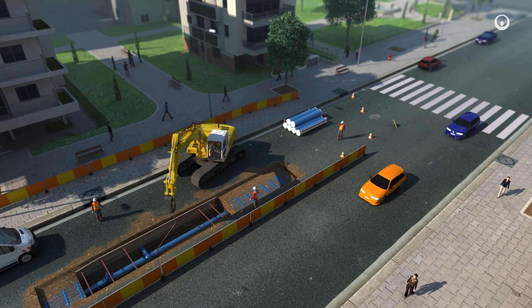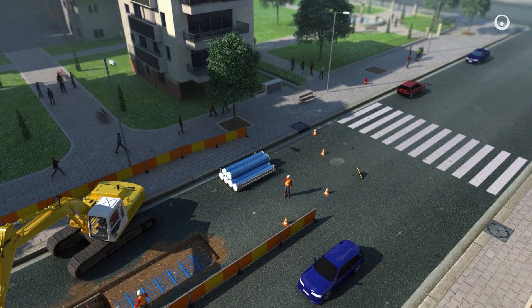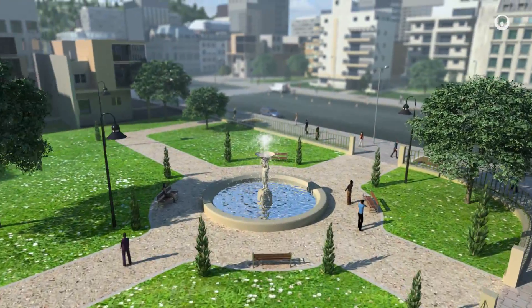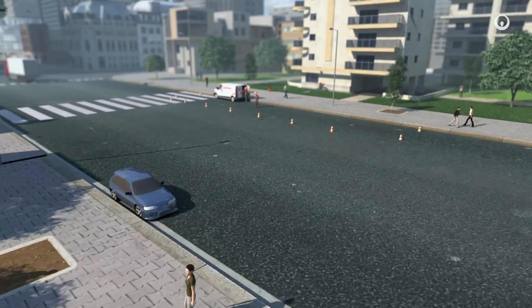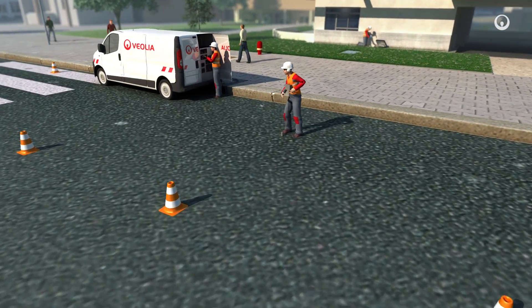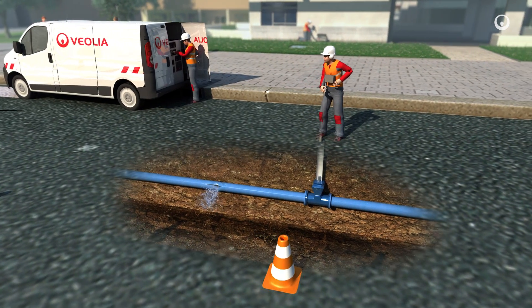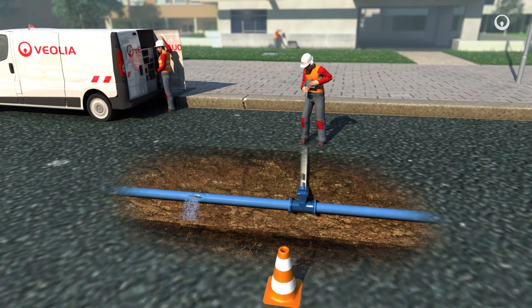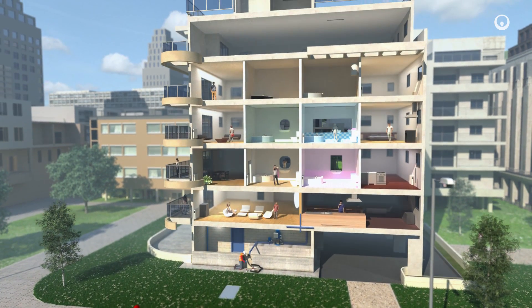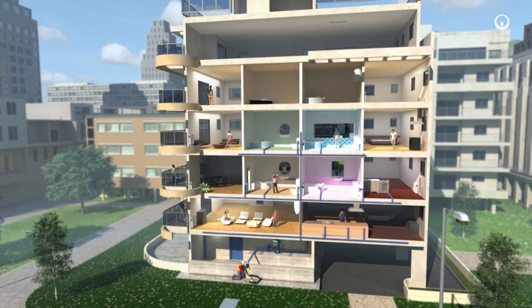Special devices and equipment help to regulate water pressure according to fluctuating levels of consumption. The system is managed in small zones, which makes it easier to diagnose problems, do maintenance work, and accurately measure water distribution and consumption volumes. This is how we identify water losses. Leaks are found thanks to acoustic detection techniques or utilization of a tracer gas. At the base of buildings, pumping stations boost the water pressure so that it reaches every floor.